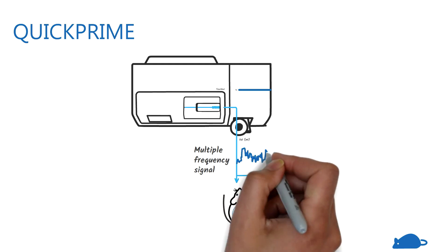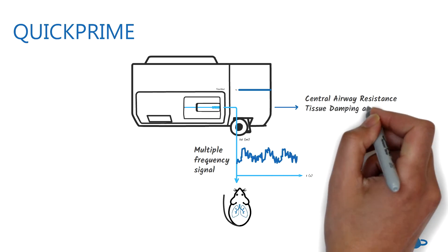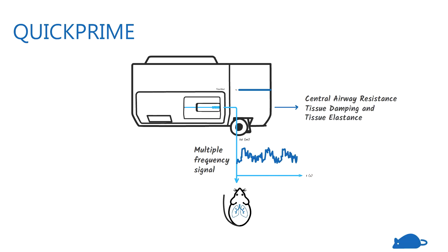In the Quick Prime measurement, the lungs are given a multiple frequency signal above and below the subject's respiratory rate. The flexiVent can then separate the contributions from the central airways and peripheral lung tissue to give central airway resistance, as well as tissue damping and tissue elastance.